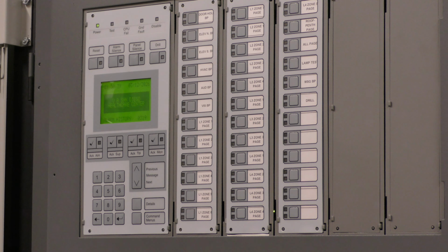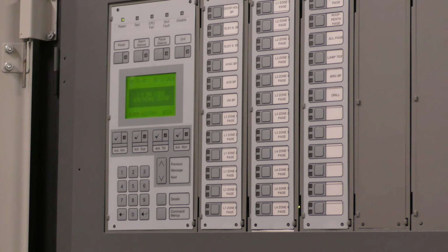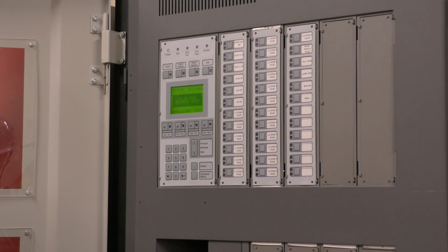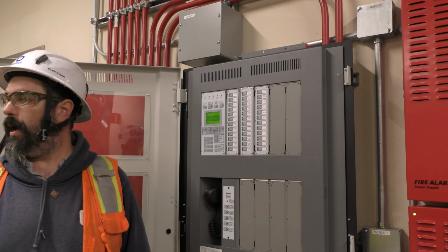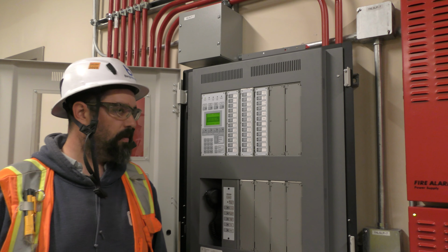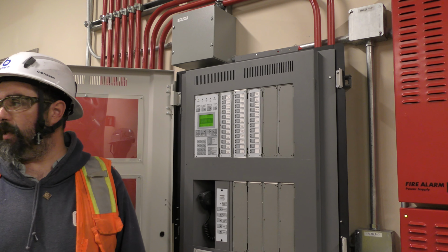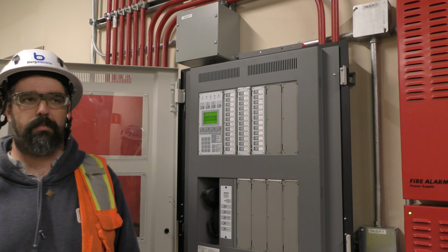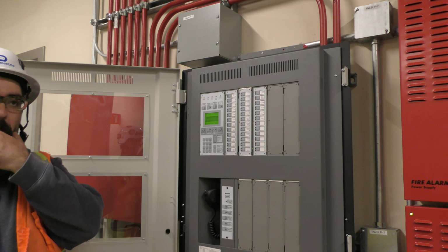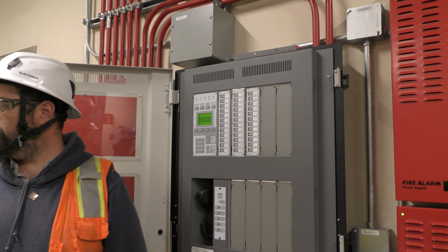Building 26. Yeah. But when you do have the main control room bypasses enabled, the LEDs will flash. Okay, so now if you're at this panel, you can know that someone's disabled something. Same thing as other buildings. And that's been tested. Yeah, we just press it down there and then verify that the LED is lit up here. We did it the day after we were doing our performance testing.